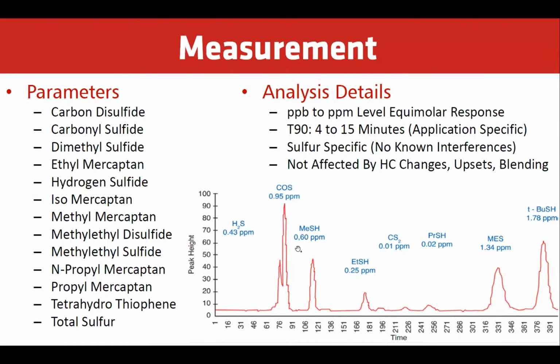So measurement again, the parameters. These are some of the sulfurs that we measure, and eventually, once we get our tetrahydrothiophene out, we backflush and we can get your other sulfurs to give you total sulfur. We can measure ppb to ppm level, equimolar response. What the equimolar means is because when we reduce all the sulfurs to SO, you're only actually dealing with one sulfur compound. We only require one standard, H2S standard or sulfur standard, in a calibration.